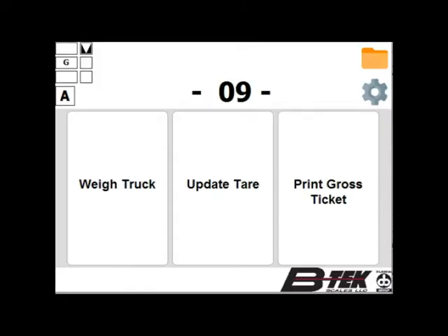When setting up a scale for the first time, you will want to see a code 09 before starting this process. If you see a code 01, troubleshoot the scale and try to find out which load cell is not connected properly. You can also perform this procedure after the scale has been set up. It will just re-correct the coefficient values for each of the cells.